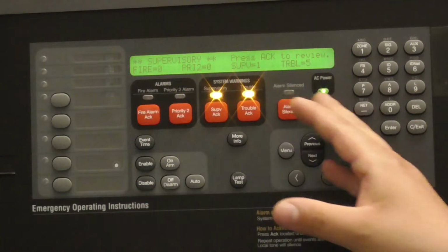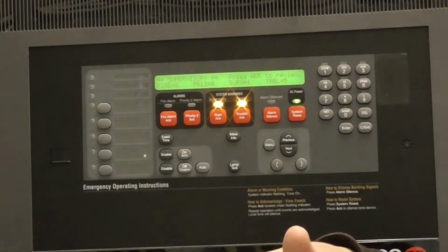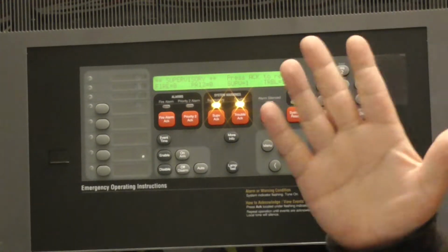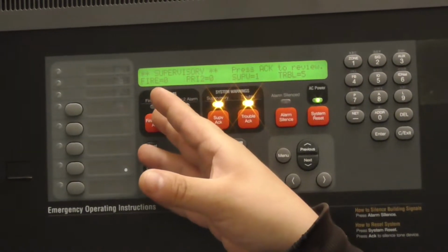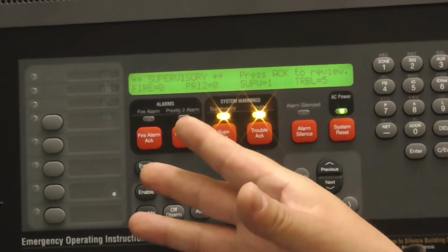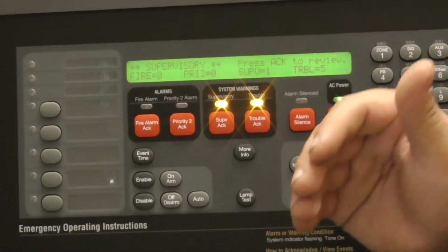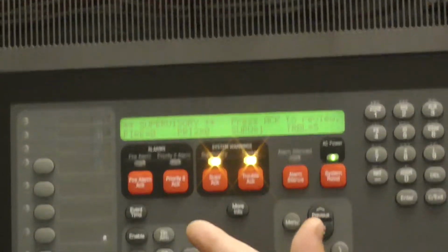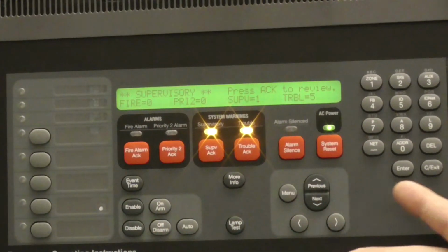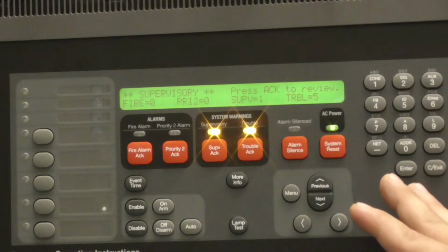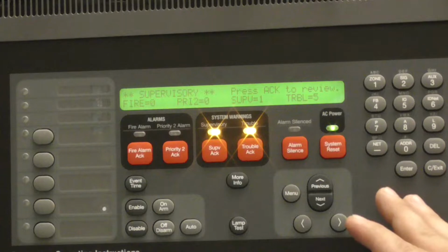So that's just the events that happen here. So like, for instance, you get a water flow, general alarm, heat detector, general alarm, or any area detection, which would be anywhere outside of the units. You'll get a general alarm on a smoke detector, heat detector, water flow, and you also have an Ansul system here. That'll go into general alarm as well. That's just the basic functionalities of it.